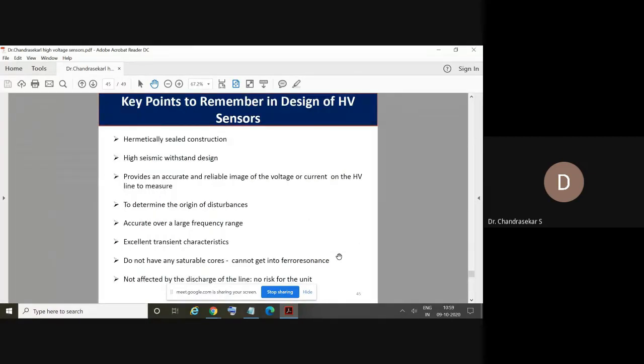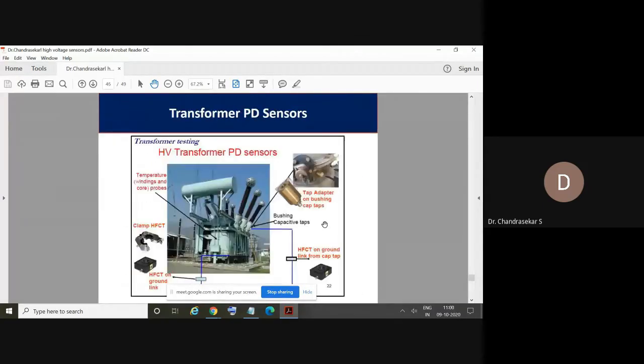So the key points to remember in the design of high voltage sensors are: since these sensors are located for outdoor applications, naturally we need to have a hermetically sealed construction, and it should have a high seismic withstand design. Whatever we are measuring, the accuracy and the reliability should be good, and at the same time it should be in a position to find out where the origin of the disturbance or the fault is occurring. It should operate over a large frequency range and have excellent transient characteristics. It should measure the very short duration pulses occurring inside that equipment. And most of the time, since we are going for inductive type of measurement, the core should not saturate, and also it should not lead into ferroresonance problems. Therefore, we need to design the core in such a way that it does not get saturated, and it should not be affected by any discharge or short circuit in the line. So these are the important points we should remember during the design of high voltage sensors.